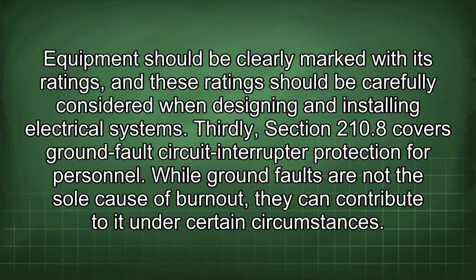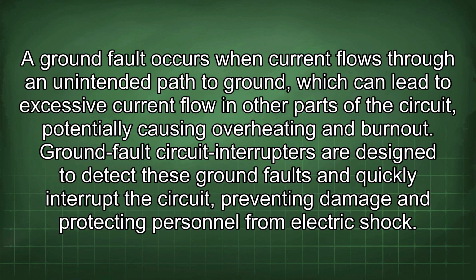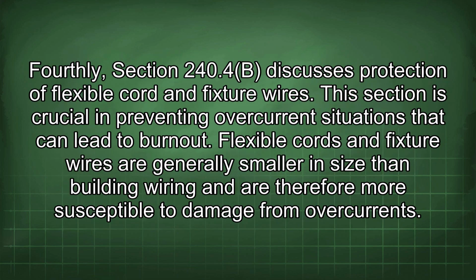Thirdly, Section 210.8 covers ground fault circuit interrupter protection for personnel. While ground faults are not the sole cause of burnout, they can contribute to it under certain circumstances. A ground fault occurs when current flows through an unintended path to ground, which can lead to excessive current flow in other parts of the circuit, potentially causing overheating and burnout. Ground fault circuit interrupters are designed to detect these ground faults and quickly interrupt the circuit, preventing damage and protecting personnel from electric shock.